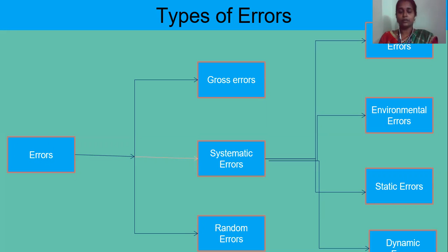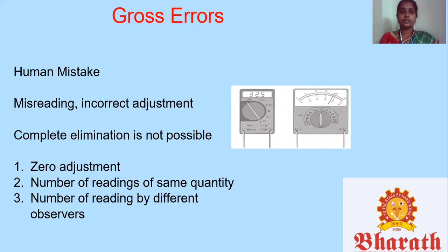So first is gross error. Gross error is nothing but when human beings are involved in the measurement, gross errors will inevitably be committed. Gross errors are due to human factors such as misreading of instruments, incorrect adjustment, and improper application of instruments. Complete elimination of gross error is very nearly impossible in analog meters. These errors can be reduced by zero adjustments before starting the experiment, by taking a number of readings of the same quantities, and by having a number of observers take readings. It is recommended to take at least 3 separate readings at different times.